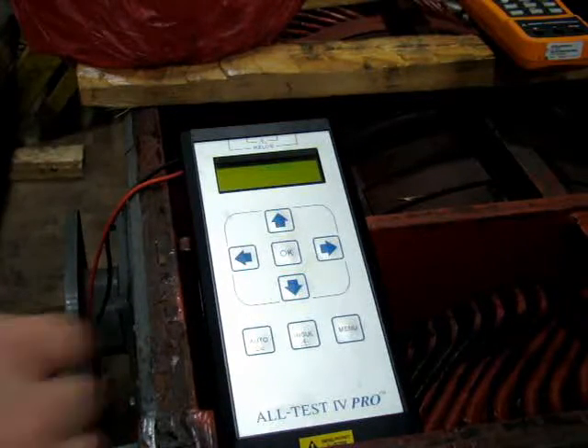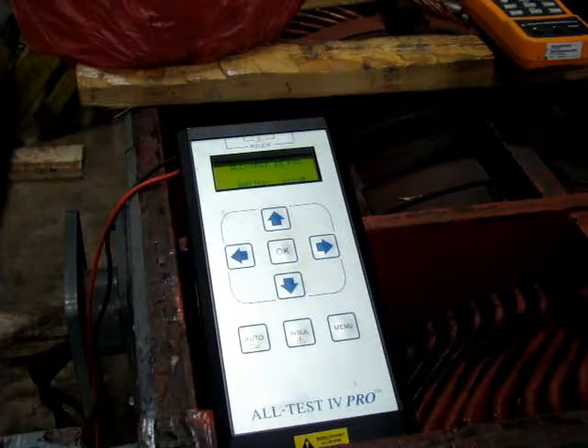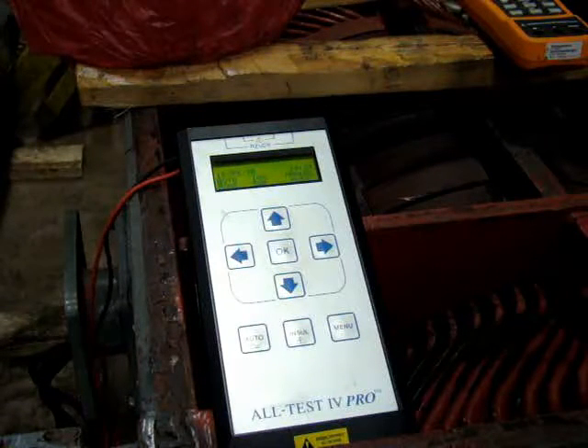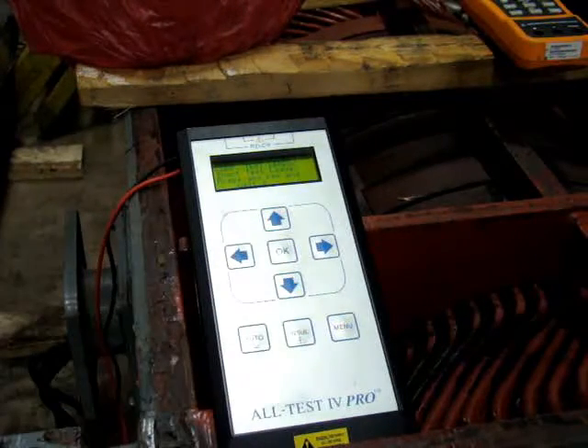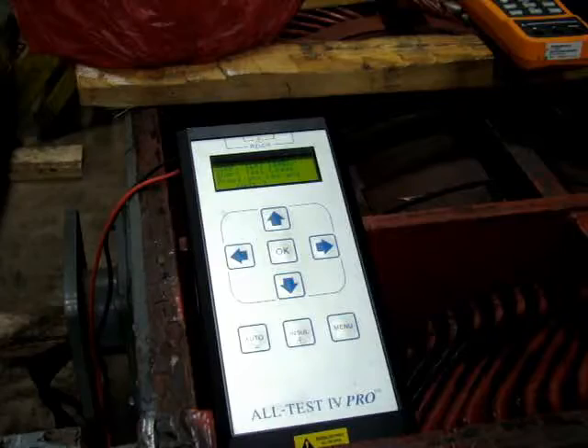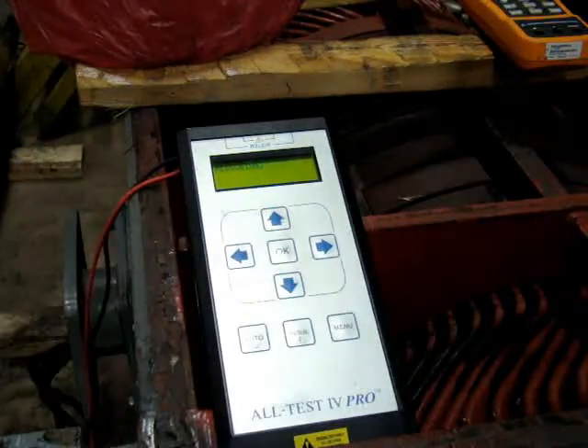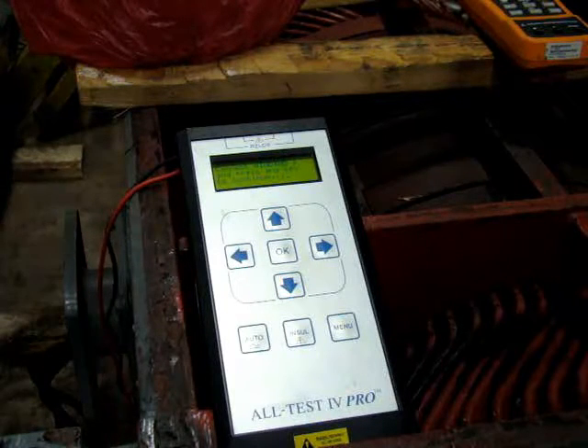We're first going to do an All-Test IV without any short, then follow it with the Agilent LCR meter without any short, and then we're going to introduce the turn-to-turn short in a single coil. In auto mode, short the leads together and connect to winding one, which is only three leads on this motor — it's a stator only.